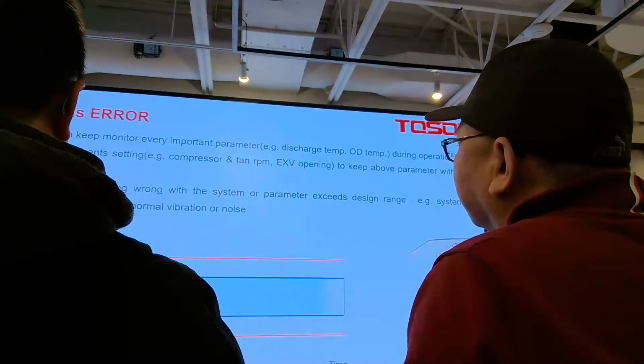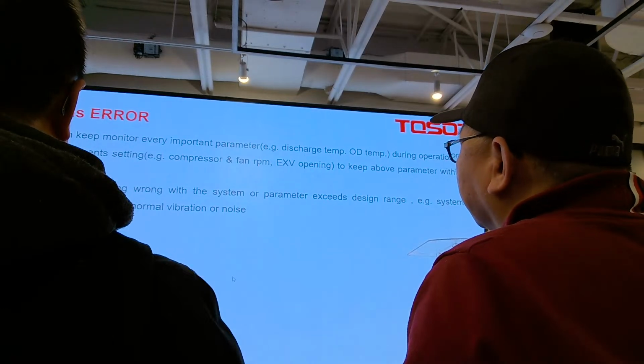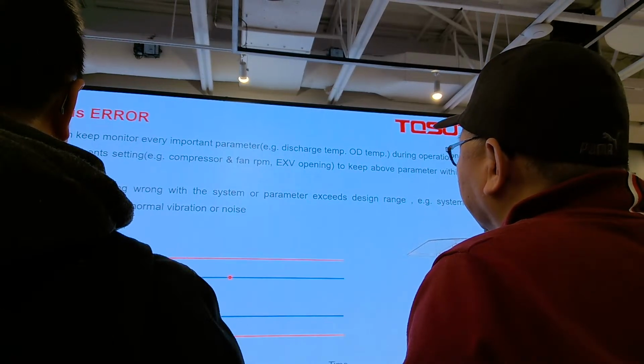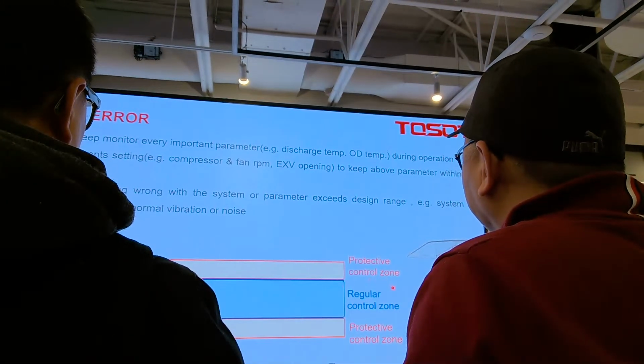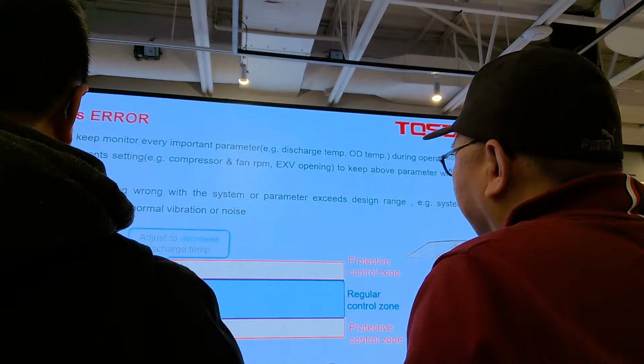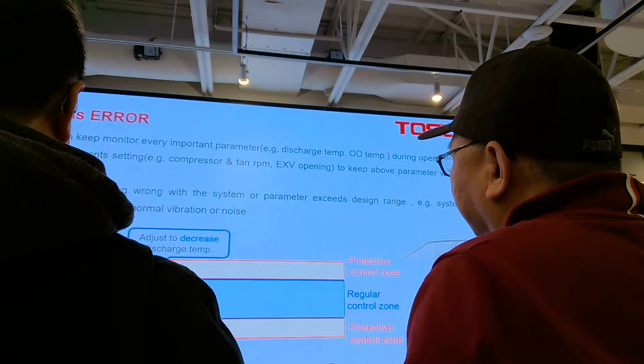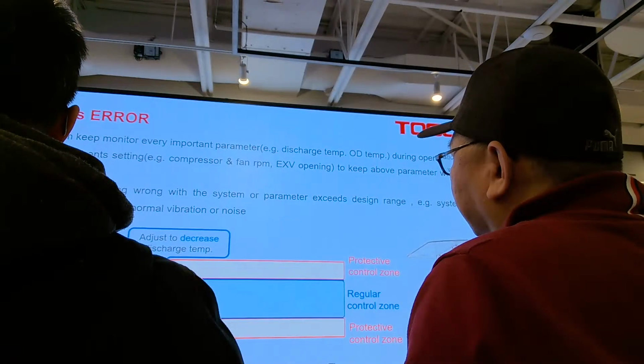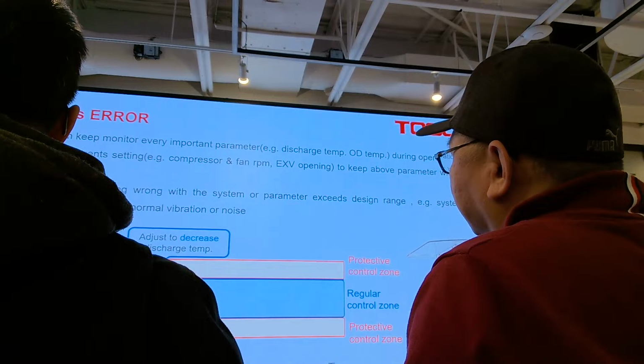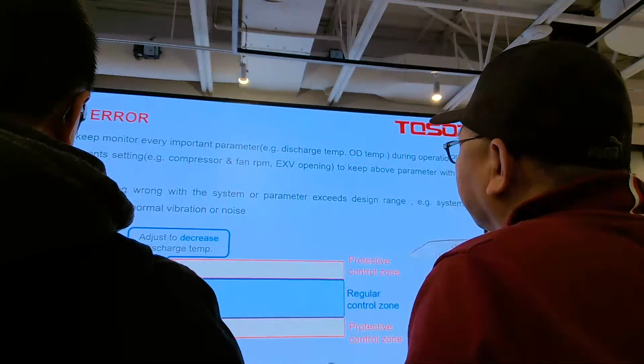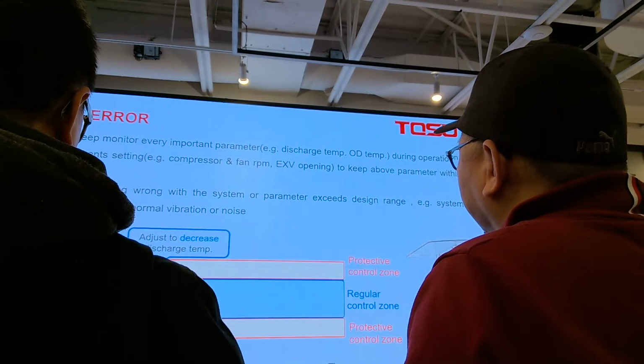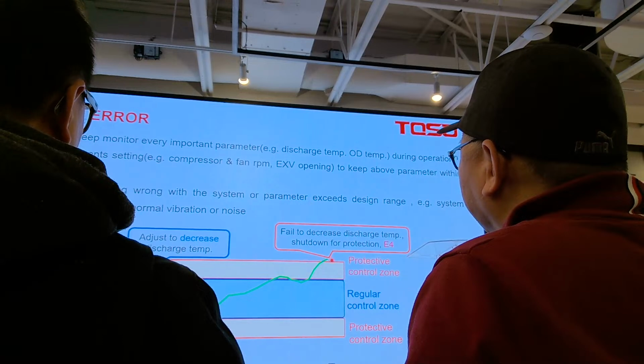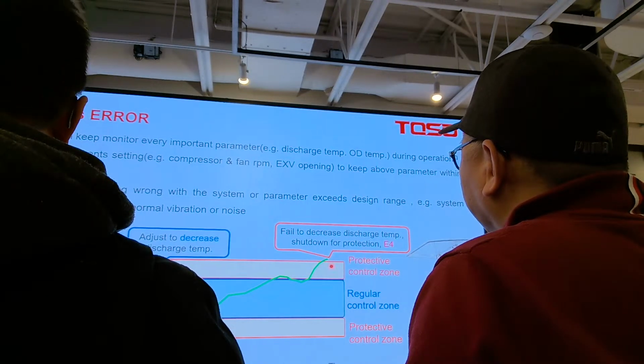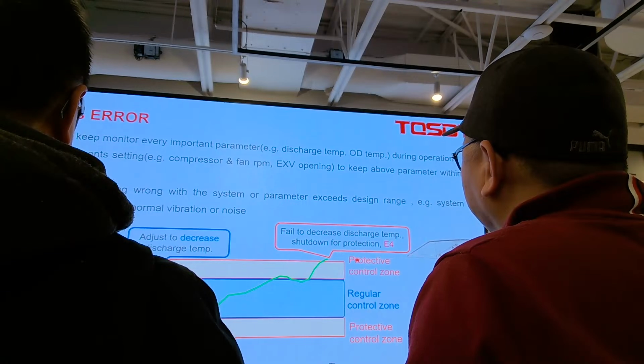So let's say, just like this one, we have the regular range and also the protective control zone. Let's say the compressor discharge temperature exceeds this or enters this protected zone. We will apply some solution, like lowering the compressor frequency or increasing the refrigerant flow rate to cool down the compressor, which means make it go down. And if it's too low, we also have another solution to make it become higher. And if it is in this protected zone, we need to stop the system and report that something is wrong to bring your attention, because if it continues to operate, it will damage the compressor or make it malfunction.